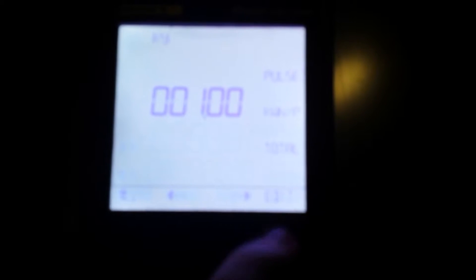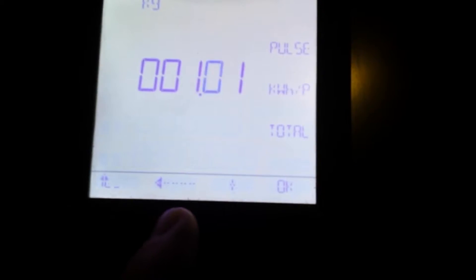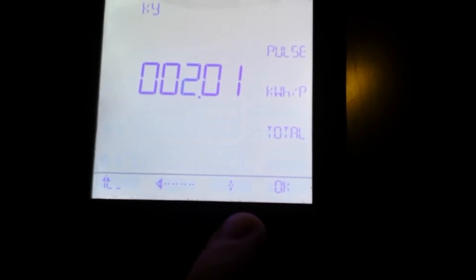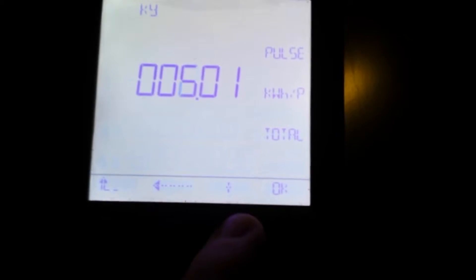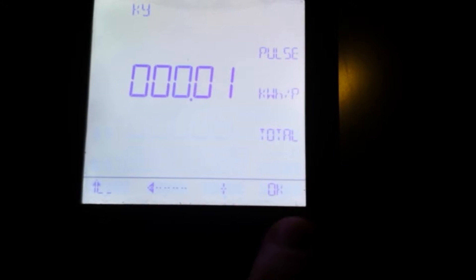We're going to increase the resolution on that because there is a very light load on this. I'm going to press my edit button. You see the pulse flashing - I'm not changing that, so I'm just going to press OK. I'm going to come down here and press the up arrow to increase that to one. It's going to be 0.01 kWh per pulse. I'm then going to press my over arrow, press it again, and then I'm going to run this all the way up until it goes back to zero. Once I get that at zero, I press OK.